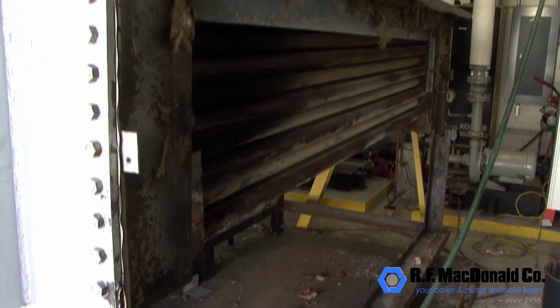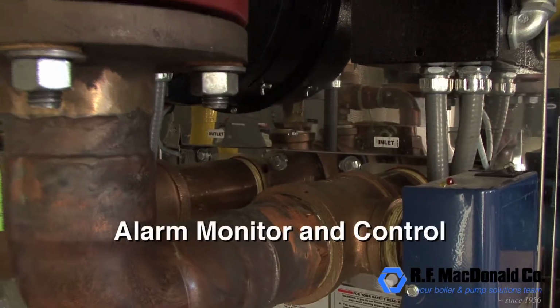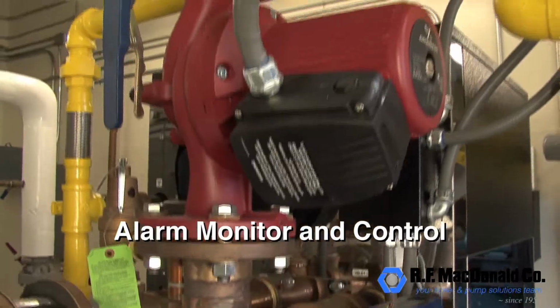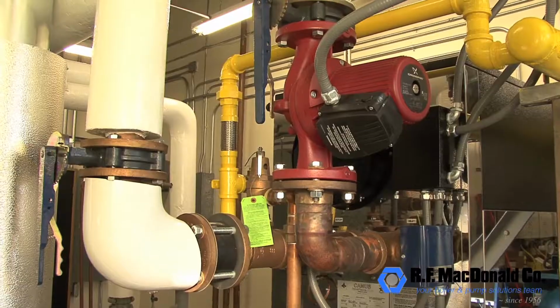So this system obviously wasn't here in 1984 when the original boiler was in. Right. What were you able to do with that old boiler before the Camus? The original system was a glorified time clock, basically. It just turned it on, turned it off, and locally it would monitor certain set points that you put into it. If something were to go wrong, would there be a fault that might show up and alert you to go upstairs? We have all our alarms activated, and if we go above or below certain limits that I program into this system, we get a little alarm light. The system's also capable of emailing us and letting us know through email that something has gone wrong.